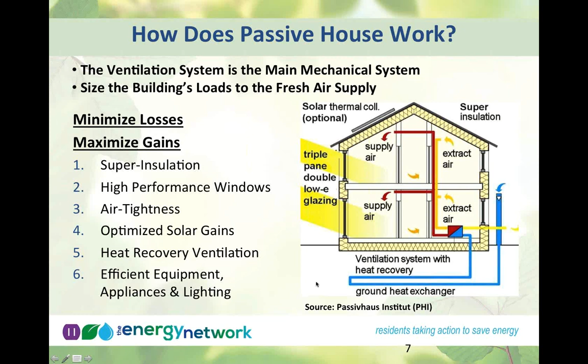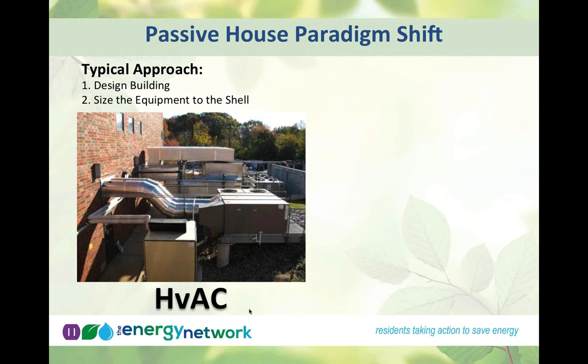Passive house represents a paradigm shift in building design. Typically, you design the building and then calculate how much heating and cooling it needs, then size the equipment to the building you have. I put HVAC with a lowercase v - particularly in residential construction, we pay much less attention to ventilation than to heating and air conditioning. By contrast, in passive house we have H capital VAC, so ventilation is the first concern.